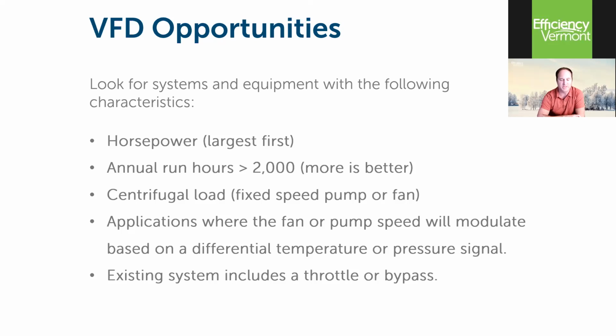Run through the series of questions. Is this a centrifugal load? Can it be slowed down? If the answers are yes, proceed. If the answers are no, move on to the next lower horsepower. We're looking for stuff that has run hours in 2,000 hours a year and above. There are 8,760 hours in a year, non-leap year. So 2,000 hours is roughly 25% of the time, a little less than 25% of the time, and more. Most of your HVAC equipment is going to run in the 2,000 to 5,000 hours a year range. So again, that's just underscoring that those pumps and fans are kind of the sweet spot for VFDs.